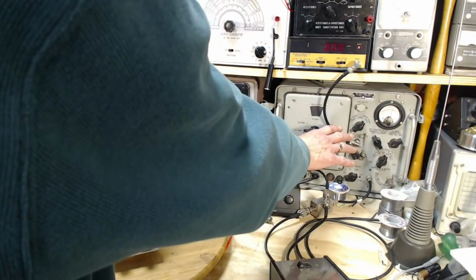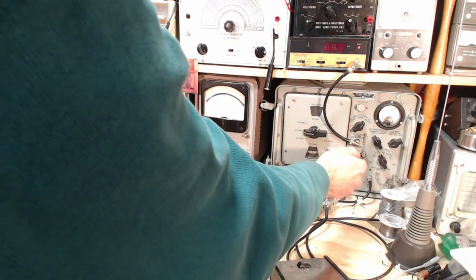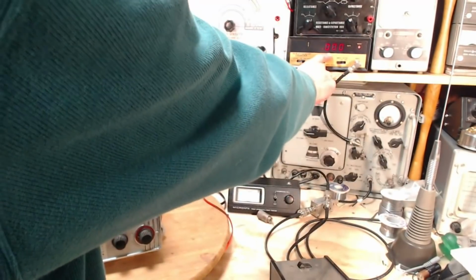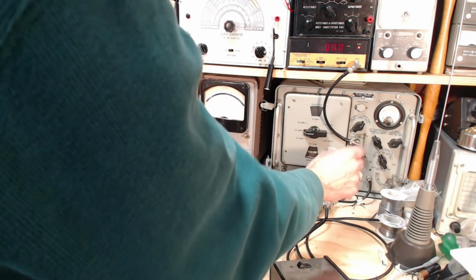This supplies now a calibrated signal to this selector down here. We check the calibration by flipping this knob to CW, making sure this meter is reading 10 with this control at max, and this is the one we adjust to get a reading of 10. This means now that this control can be direct read when this switch is in this setting, but we can't read the frequency. But that won't matter. Once I have this set, we don't need to read the frequency. So we can flip it into a calibrated mode, and I know for sure, this is pretty high now, let's turn this down. So that would be X times 10.